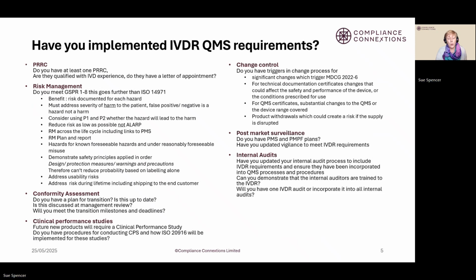So we talked about there's no transitions for new devices. Clinical performance studies are expected for new devices. So you need to make sure that you've got procedures in place. You may have not used them yet, but what is your process going to be for doing those clinical performance studies? And also, I often see that manufacturers aren't talking about ISO 20916, which is how you would conduct those studies. So that needs to be visible in your quality management system.